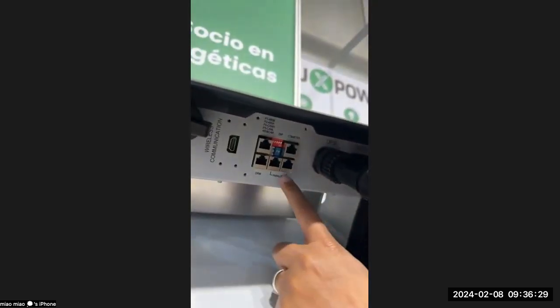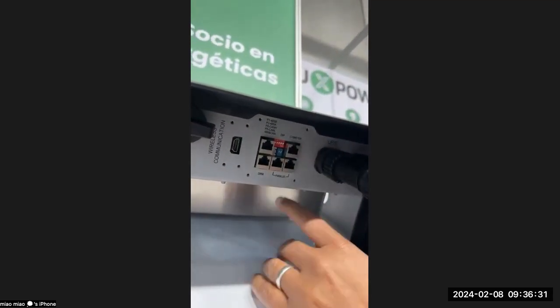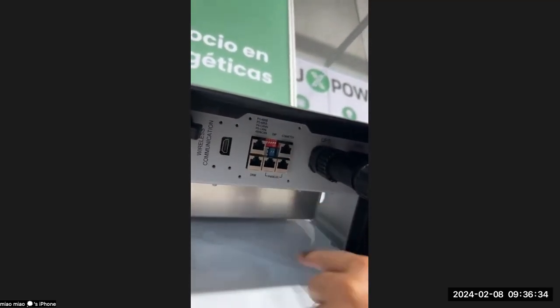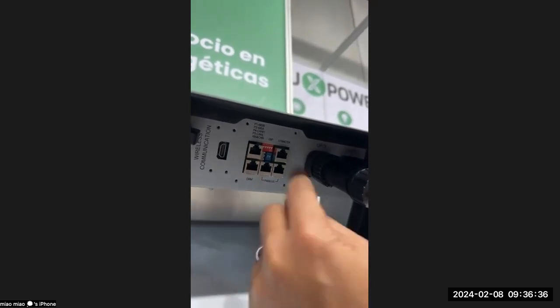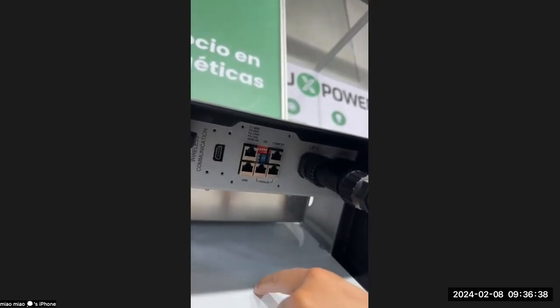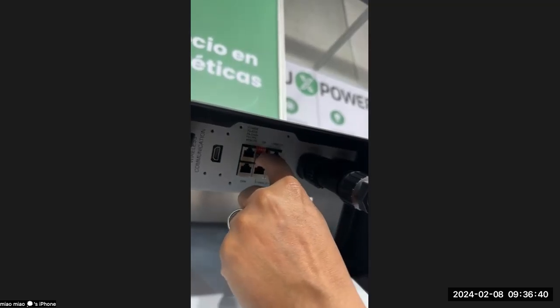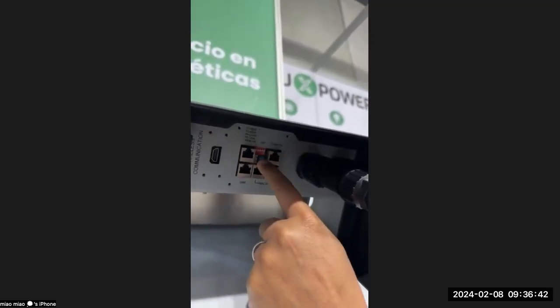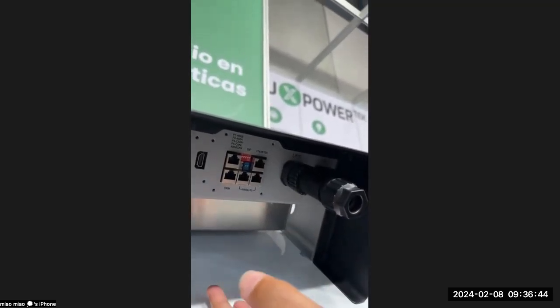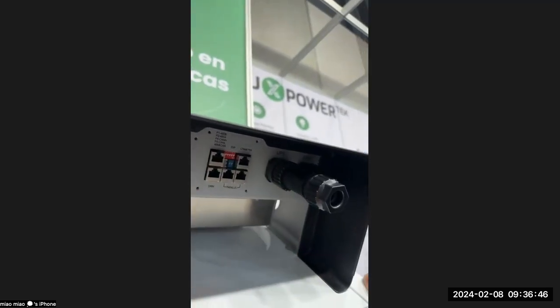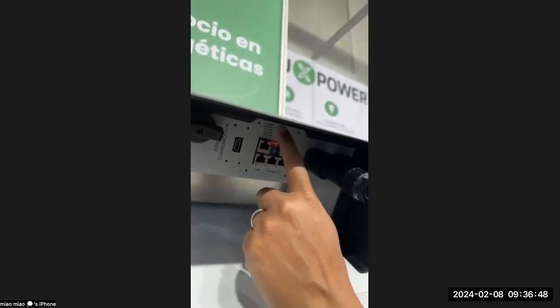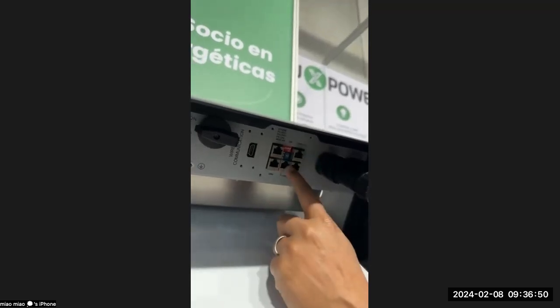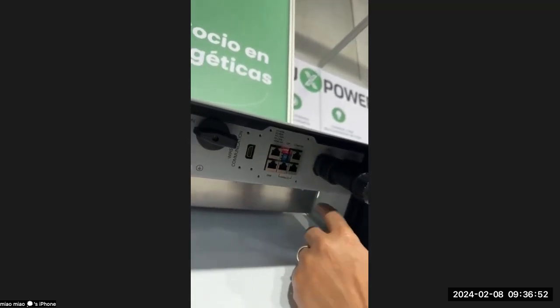If you have one machine, no need for this. If you have two machines, you're going to go from this port out, and you'll come into that port on the second machine. So you're creating a loop. And then the dip switches here for paralleling, you have to put both machines on. If you have three machines, then the first machine on the left will have the dip switches on, the middle machine will have the dip switches off, and the end machine will have the dip switches on.